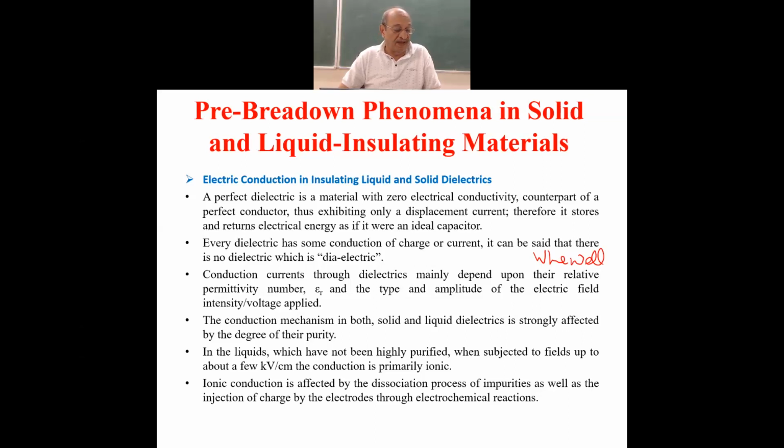So the accumulation of charge, maybe at the electrodes or anywhere, will also affect the pre-breakdown currents. Then particularly in solid dielectrics, there may be some mechanical stresses developed within the dielectric, mechanical pressure or tension, and they will determine the pre-breakdown current.